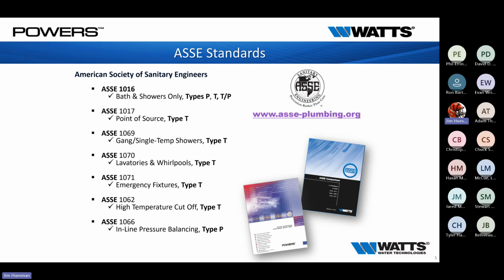To about 120. And remember, we've jumped down to our emergency mixing fixtures, the ones no one ever uses. But when you have to use that eye wash - one time in my career I got PVC cleaner in my eye, and I was really happy when I turned that eye wash on and didn't have 120-degree water splashing in my eyeballs. It was set at a nice cool 85 degrees, which let me sit there about 30 minutes and let the water pass through my eyes and get it cleaned up.